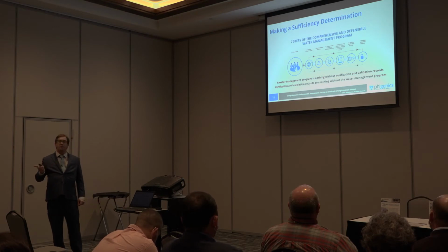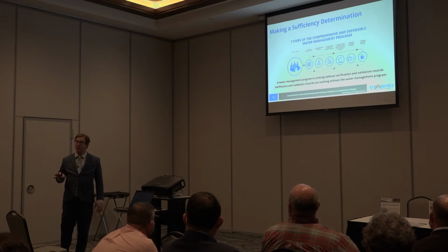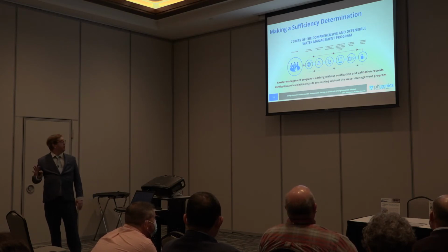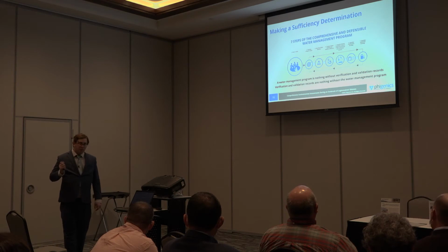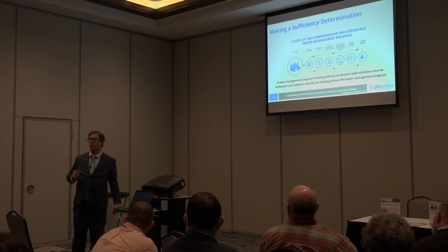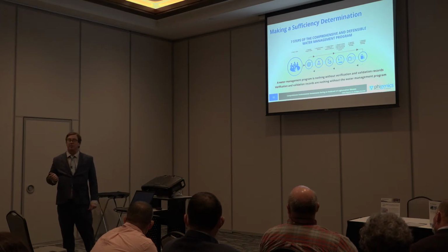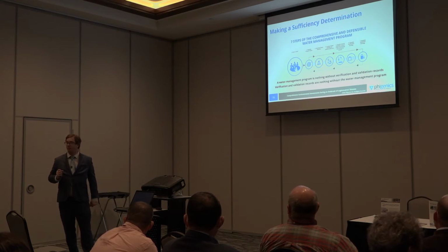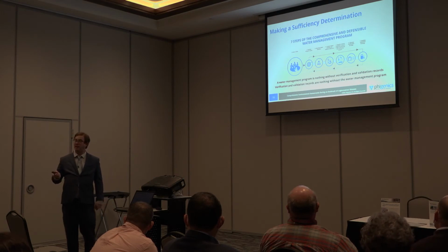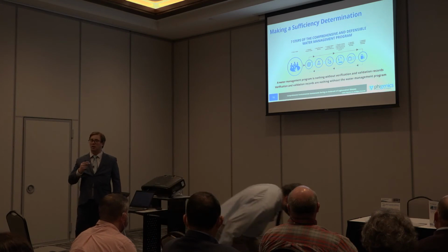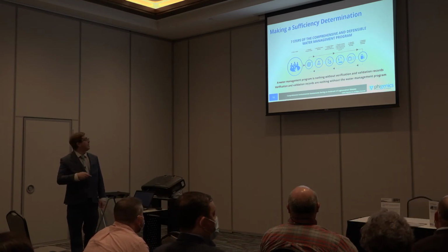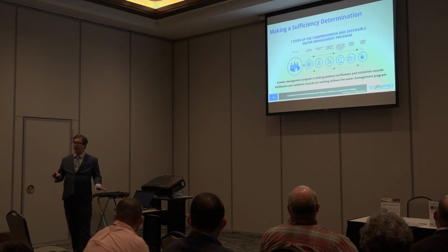And keep in mind a couple things. A water management program on its own is nothing without verification and validation records. And on the flip side, verification and validation records are nothing without the water management program. So if a facility or property manager is saying that their mitigation strategy is to test for Legionella and see if they have it, that's not sufficient. They need to have a program and they need that validation data to inform observations about the program. So it really needs to have all these steps that are detailed in ASHRAE 188.